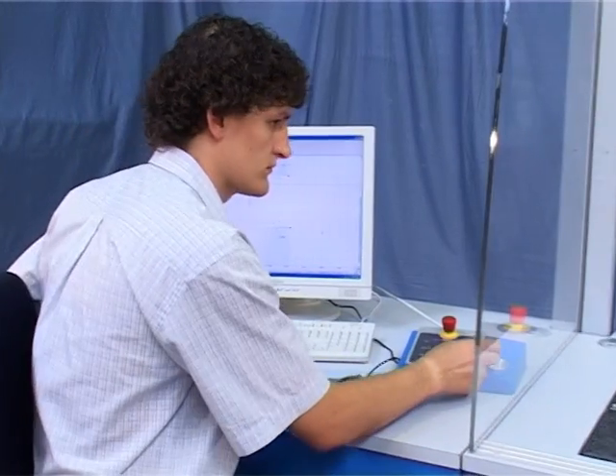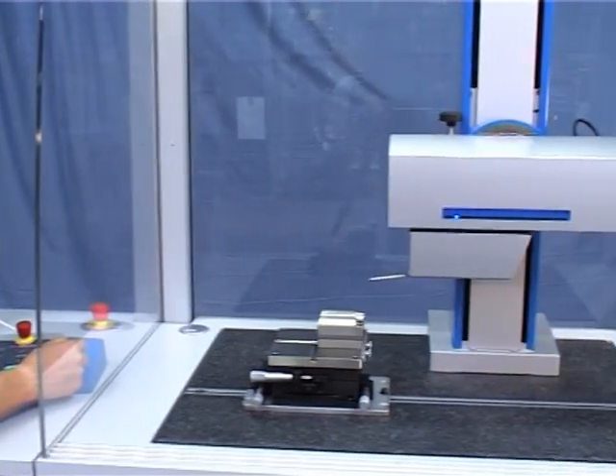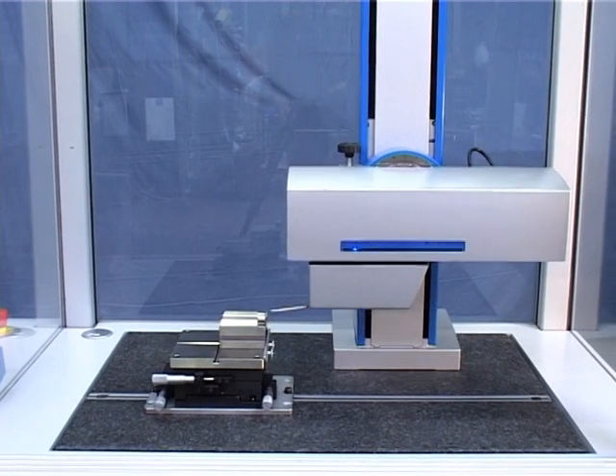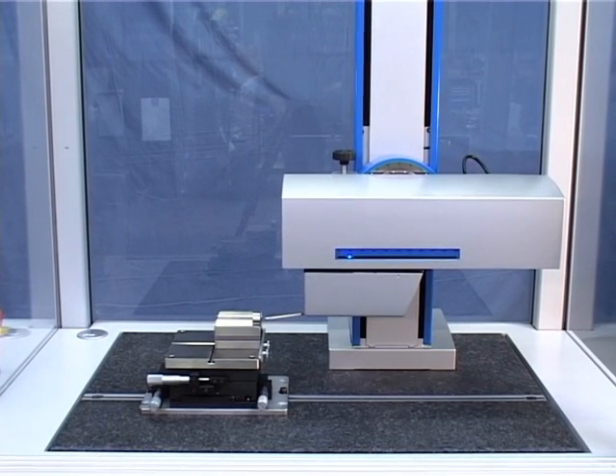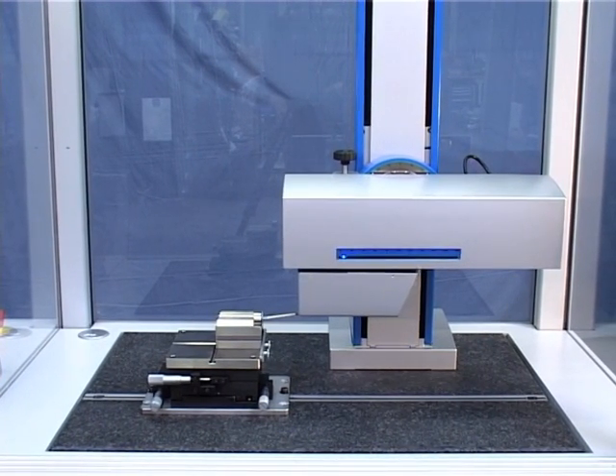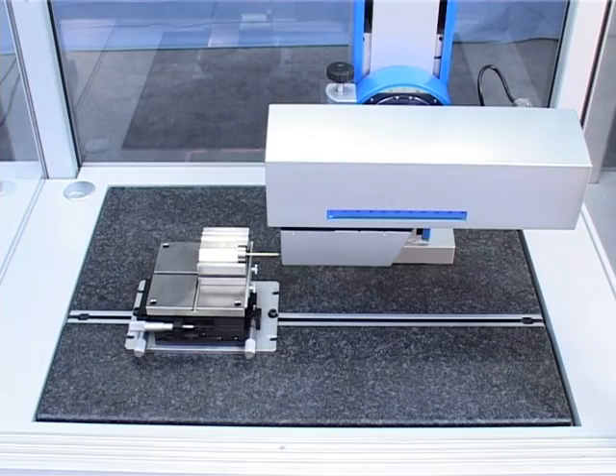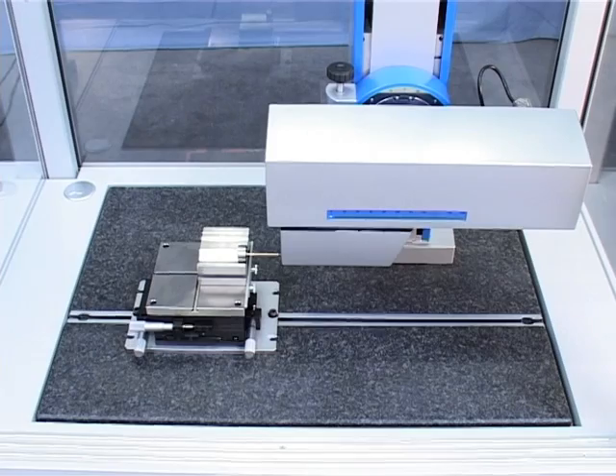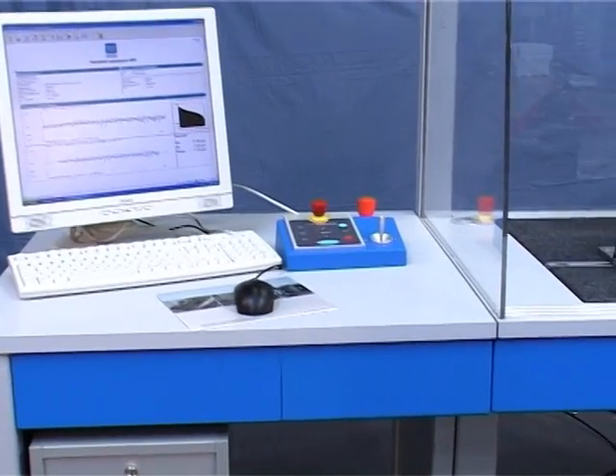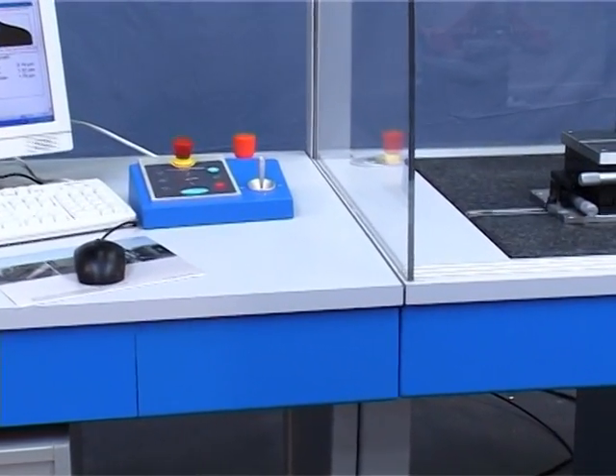The ergonomically designed measuring station facilitates user control and guarantees that measurement results will be unaffected by external influences. The measuring table with granite plate is isolated extremely effectively from external vibrations by active damping. The PC workstation is also mechanically controlled.